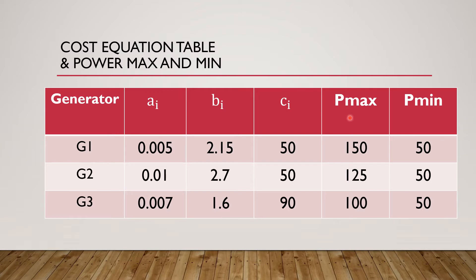Pmax is the maximum power generated by the ith unit; Pmin is the minimum power generated by the ith unit. There is a limitation for each unit on how much maximum and minimum power can be generated without loss. Here, the three generators operate at a minimum power generation of 50 megawatt. Pmax of unit 1 equals 150 MW, Pmax of unit 2 equals 125 MW, and Pmax of unit 3 is 100 MW. So the maximum power from all three generators is 375 MW and the minimum is 150 MW.